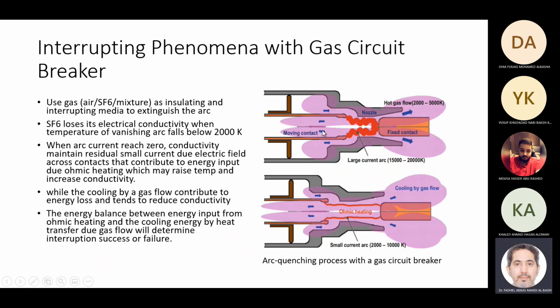And the second theory is based on the energy. Like in SF6, the gas has very good dielectric properties, but it's also used to cool the arc. On the left-hand side, this shows you the fixed contacts, and these are the moving contacts. This is the moving contact. Initially, this was inside here, so there is continuity of current through these two terminals. When you open this moving contact and move it away from here, the arc is initiated, and the pressurized SF6 gas passes through this nozzle, goes here, and also goes inside here.